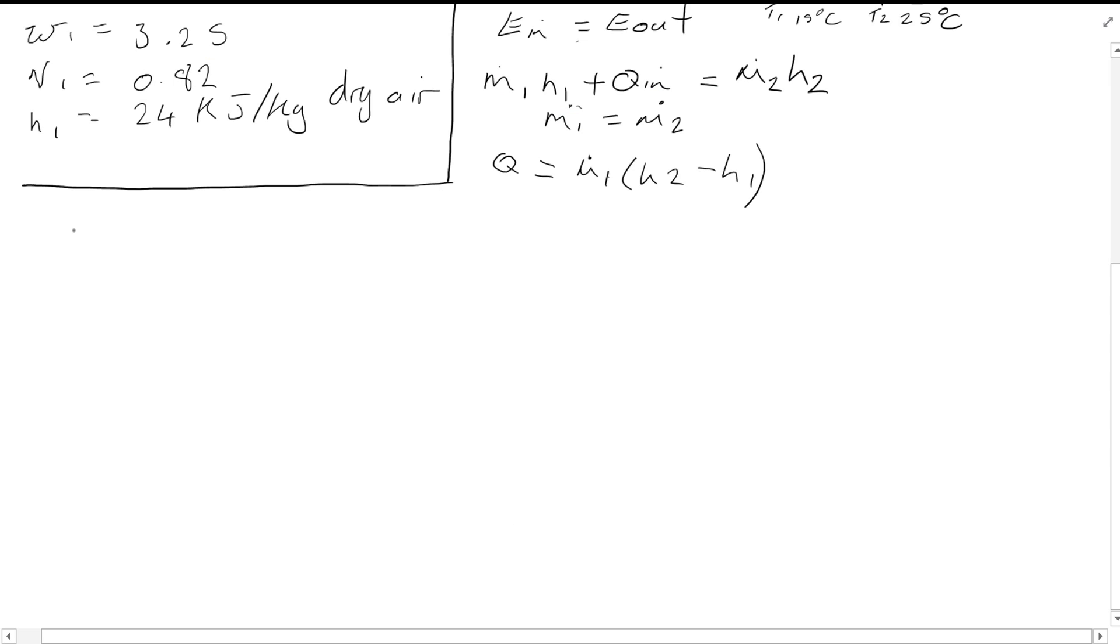Similarly, at point 2, because we know W1 is equal to W2 equal to 3.25, and because we know the temperature at 2 is given at 25 degrees, we also have two values. So we can also find the enthalpy H2, which is equal to 54 kJ per kg dry air.